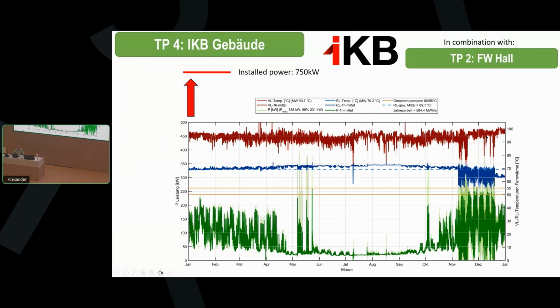This is fine. But on the green lines here, you see the power on the left axis. The dark green is the 1 hour average, and the thin light green is the 15 minute value. And as you can see, we are talking about 200 kilowatts here. Here we come a little bit higher, 250 kilowatts, and installed we have 750 kilowatts. So it's 3 times more, wasting a lot of money just because of having too much power.